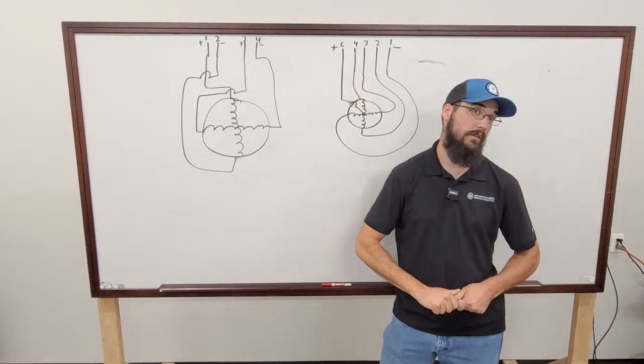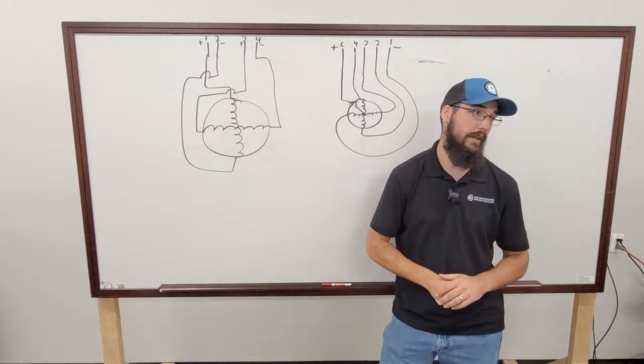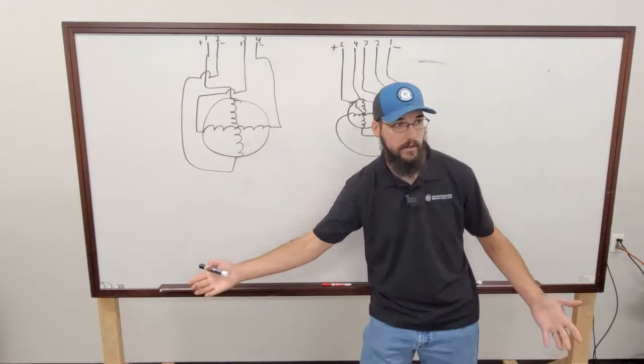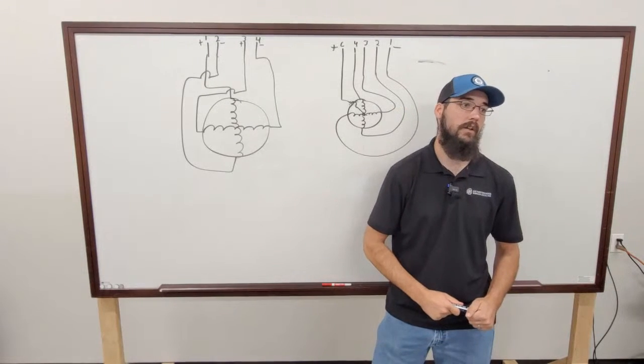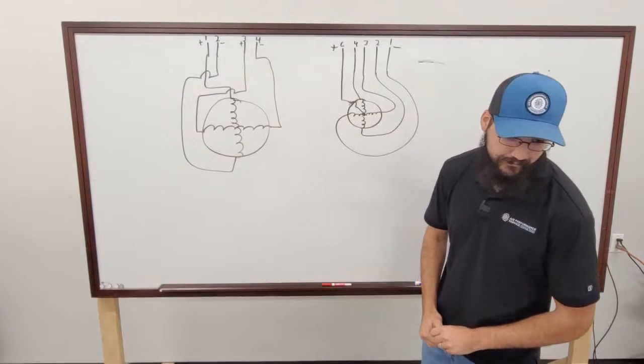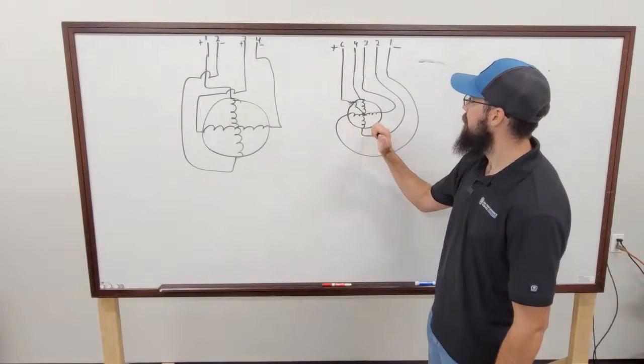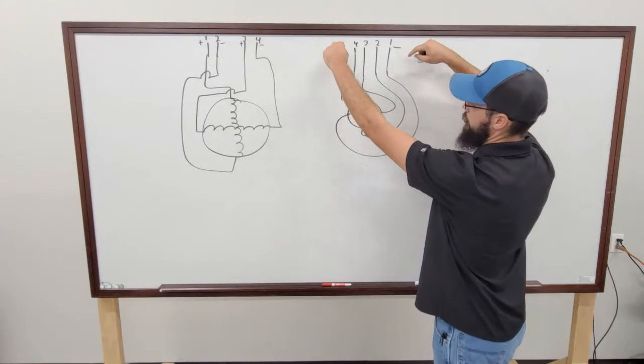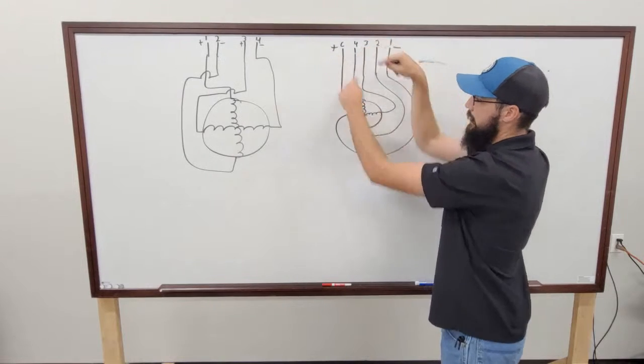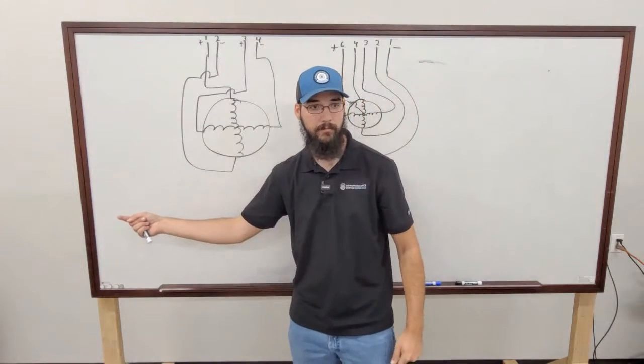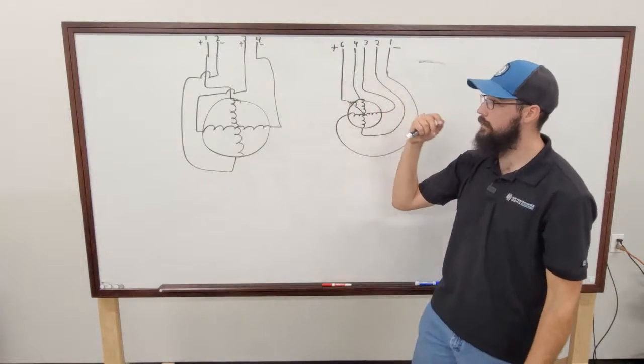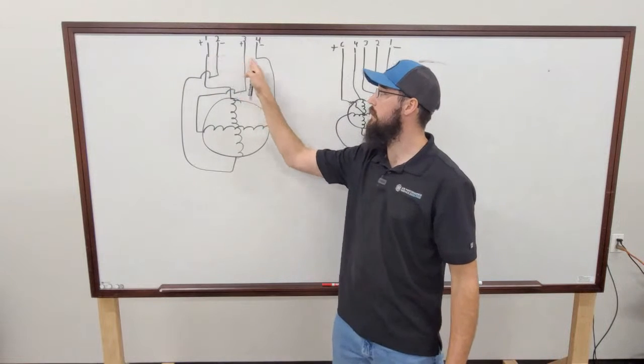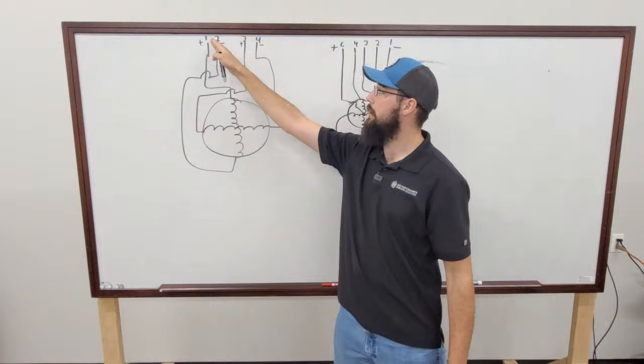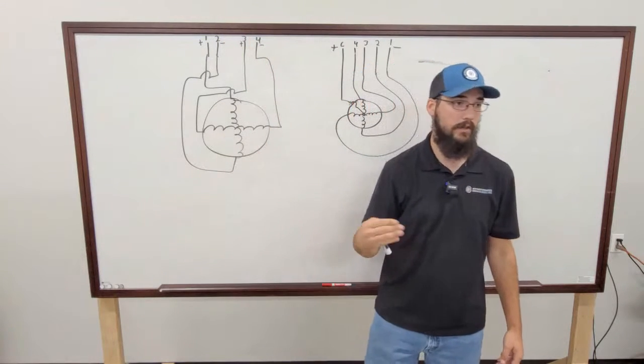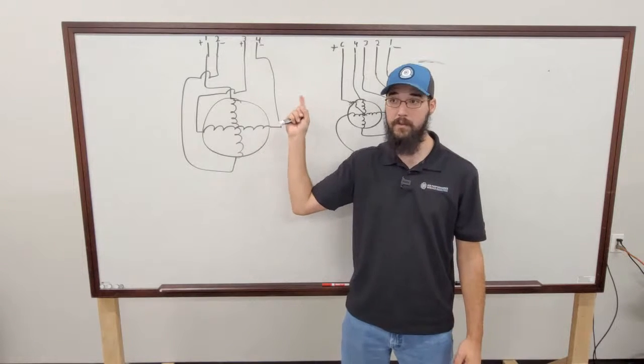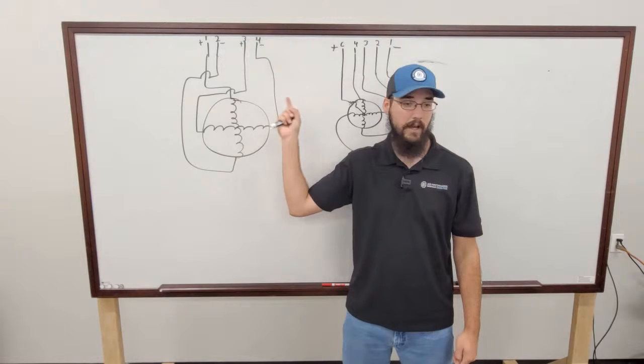Sporlan, yeah, York and Train both use Sporlan and Danfoss depending on the series and application and revision. So there's been different revision changes. Basically, cheapest bidder. So anyway, in this particular case, you would ohm from common to each of these, and each winding should be identical resistance. If you had one that wasn't, obviously something's wrong. In this particular case, if you have this style and you have resistance between the windings, something's wrong, because they should never have resistance. Something shorted internally if that happens. They do not have electrical contact.